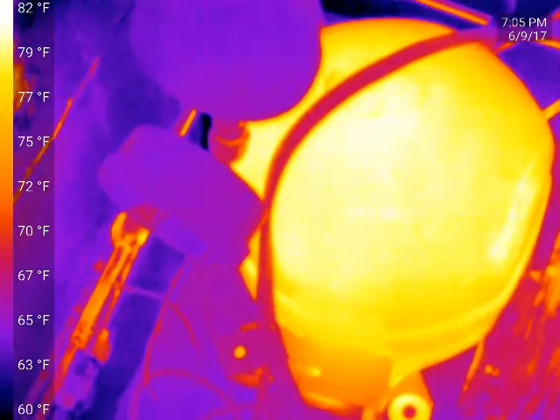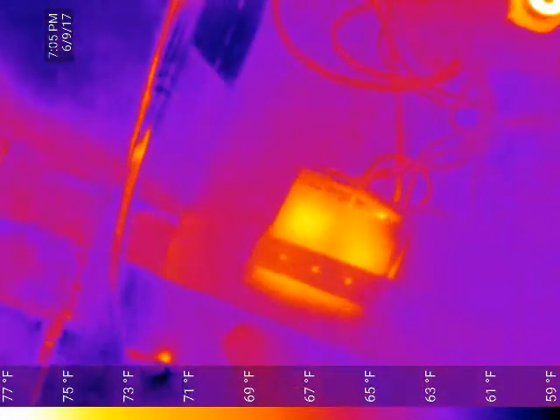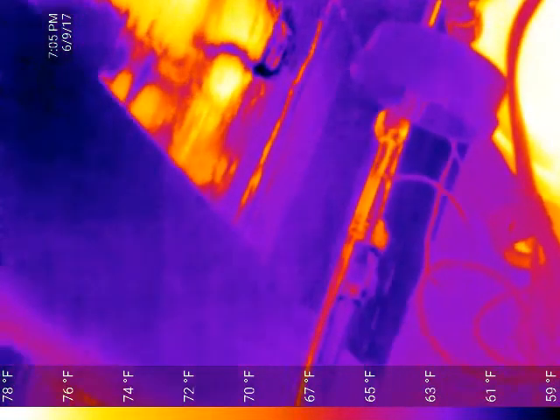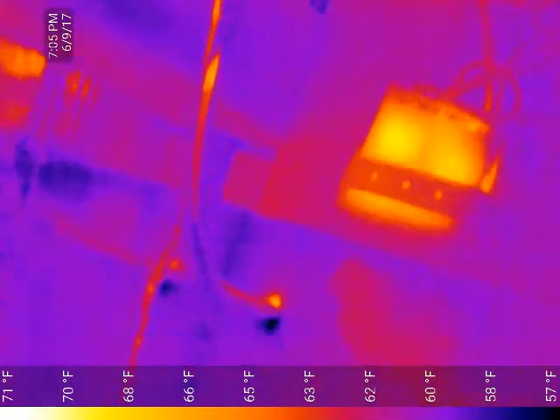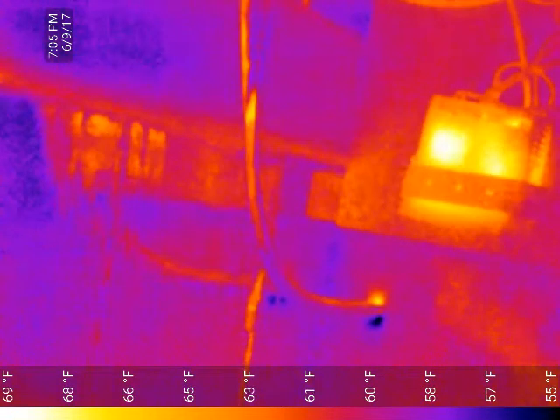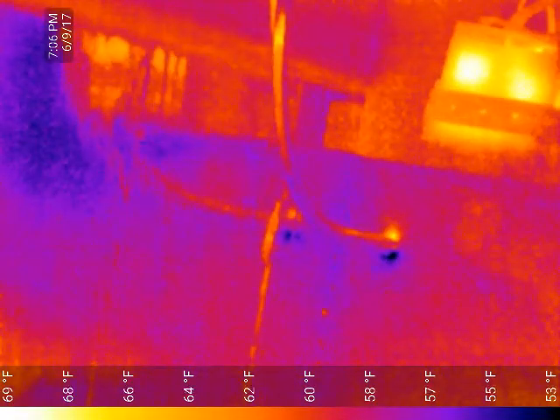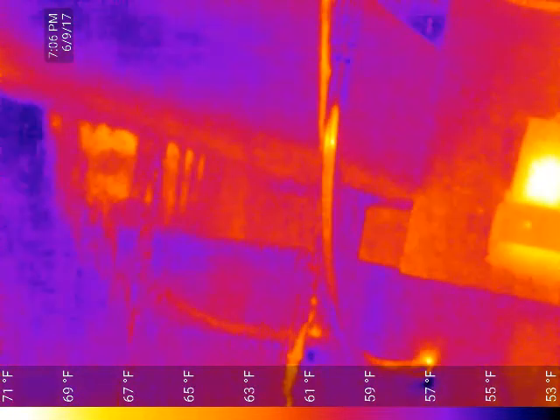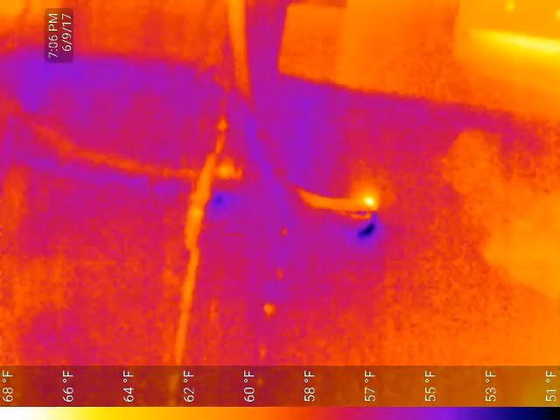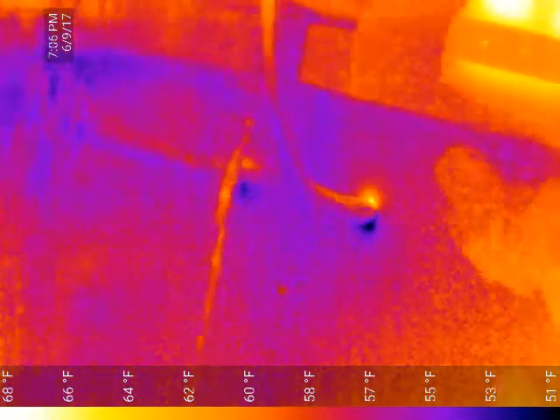It's been running for about 10 minutes now, so you can see the compressor's warm down there. These lines aren't insulated at all. There's the thermostat with the strap on it, and a reflection of the compressor. The suction line is three-eighths and the discharge line is three-sixteenths. You can see down there in the hole in the floor where they go through — the dark spot on the left is the cooler wood, and the brighter spot on the right is the warmer wood from the two lines.